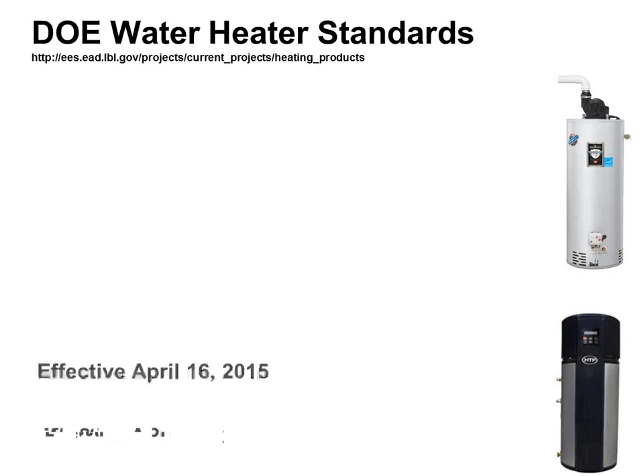We have no other technology anywhere that I'm aware of, at least in the HVAC world, for space heating or water heating that can do more than 100% efficiency other than a heat pump. So anything bigger than 55 gallons electric fuel sourced has to be a heat pump nationally by law, no other choice. So you're going to start seeing heat pump water heaters if you haven't already started seeing them already.